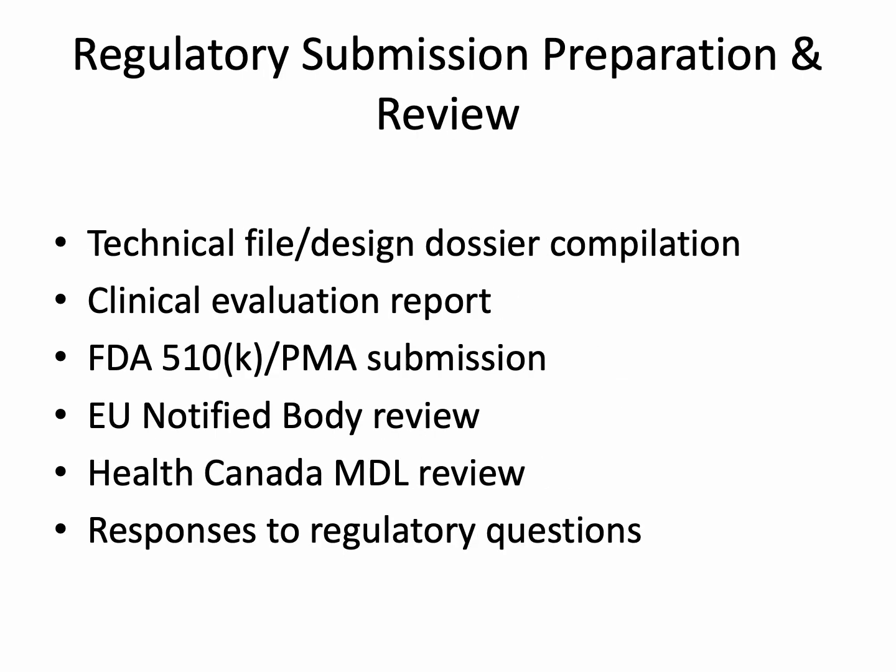Preparation for regulatory submission involves compiling a complete technical file or design dossier, clinical evaluation report, and supporting evidence for safety and efficacy. Submissions are made to FDA, 510(k) or PMA, EU notified bodies for MDR assessment, and Health Canada for MDL review. Timely and comprehensive responses to regulatory questions are critical to prevent delays and ensure approval. Coordinating submissions and leveraging common evidence across jurisdictions optimizes efficiency and resource use.